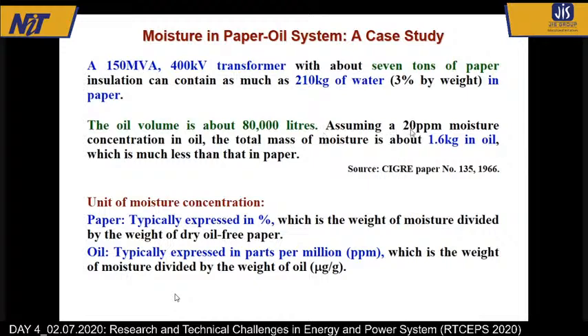And if I say that 20 parts per million is the moisture content, which is quite high, and if you convert it into kilogram, it comes to 1.6 kilogram of moisture in oil. Now that's what I want to highlight to all of you, that 3% by weight and 20 parts per million is not very bad, but it's a warning level.